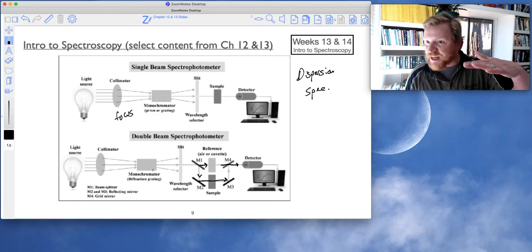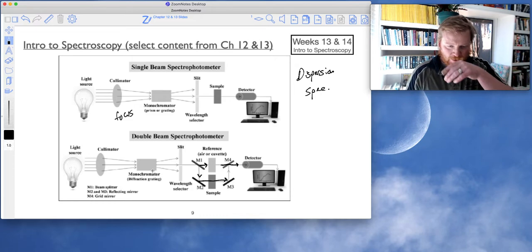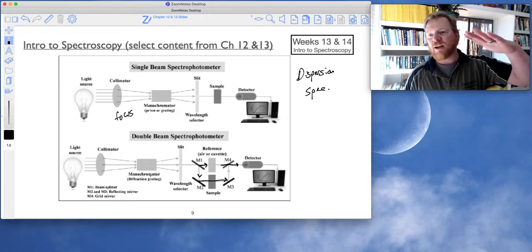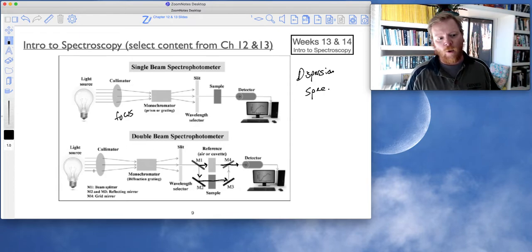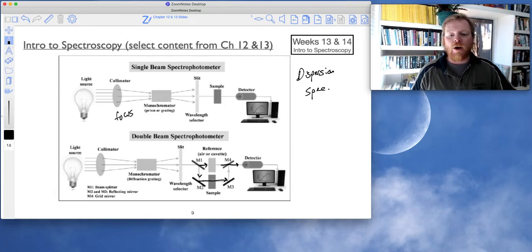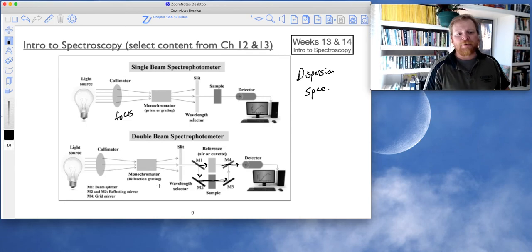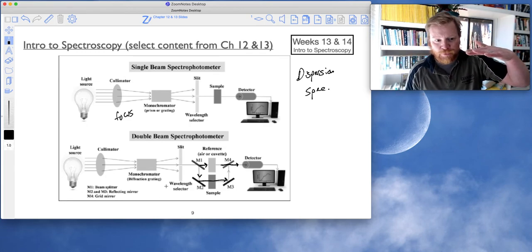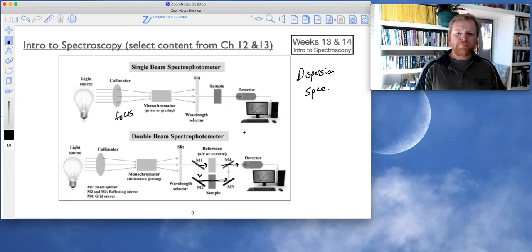So these things will scan one wavelength at a time, okay? And whether that be from angling the diffraction grating or angling the light source, or what I didn't talk about last time, we are getting to the point where we have more sophisticated detectors that can discriminate wavelengths of light. But those types of detectors still aren't nearly as good at resolving different wavelengths of light as changing the angle of our diffraction grating, okay?